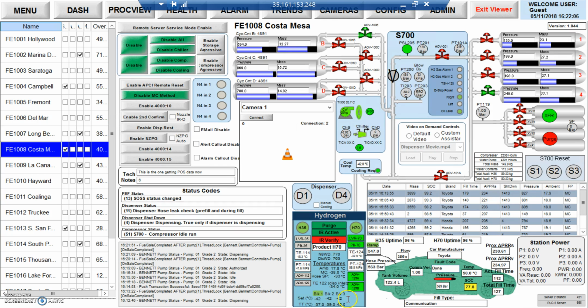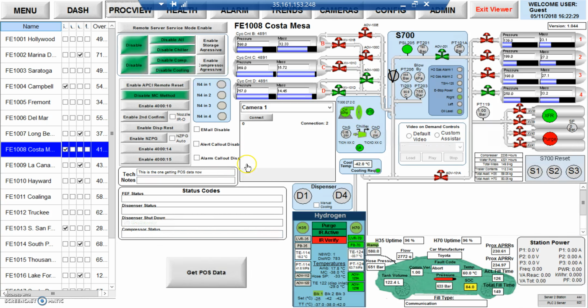Down here we see the block temperatures, and what's really cool about this is we can see all 3 blocks. What you notice here is that block 1 is at minus 37, minus 39, and minus 42. As we start to get into some issues, well, you know what? I can change this to minus 25. And I can just go back to dash and process and see if it accepted it.